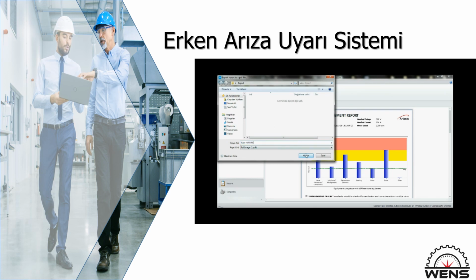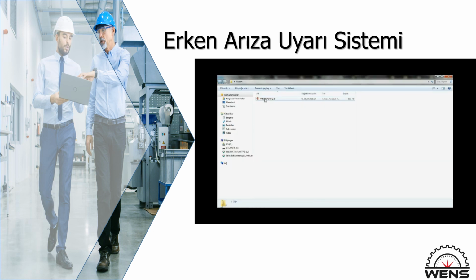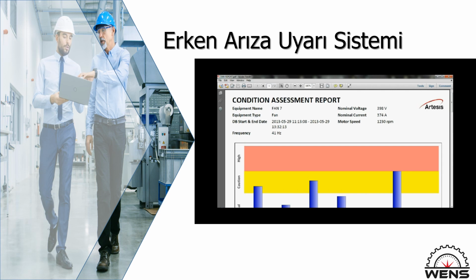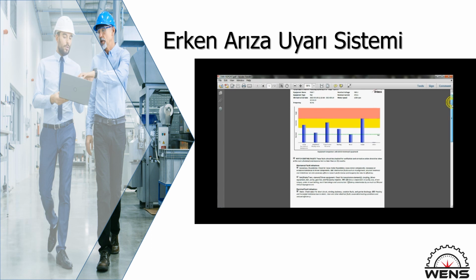If these electrical parameters are above their expected values, a warning is issued for the attention of the user. These parameters can be used to help determine efficient operation of the equipment. Many users are aware of the connection between deteriorating condition and reduced efficiency. Excessive misalignment, voltage imbalance, or mechanical imbalance can have serious impact, as can heating caused by bearing or electrical problems.